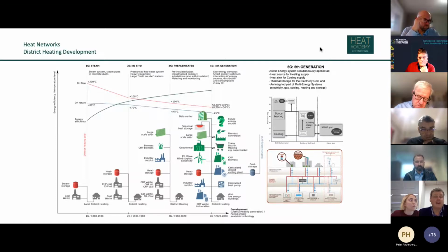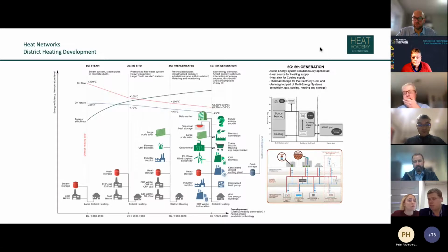These were typically categorized by steam-based systems, high temperature, low efficiency. Then it evolved over time into what we refer to as second generation district heating, with hot water typically in the range of 120 to 130 degrees supplied from one or a few production facilities to different consumers. In the third generation district heating, temperatures went down below 100 degrees, utilizing more fuels and more production technologies in one network, what we call pool-operated networks, with a number of production facilities feeding into the same network.